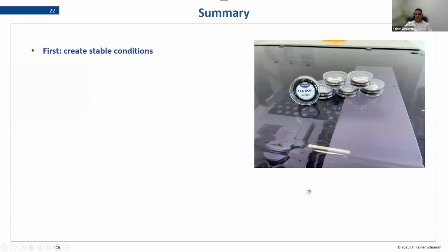So to summarize, first, in the beginning, you have to establish stable conditions. That means when you select your measurement conditions, you have to make sure that, for example, the line position settings, the PHD settings, the MCA calibration, that they are all under control so that any kind of movements there have nearly no influence on drift. So then you minimize the drift already from the beginning.